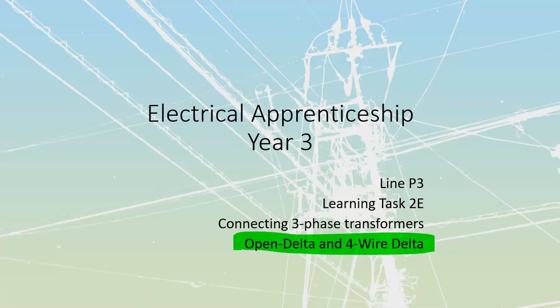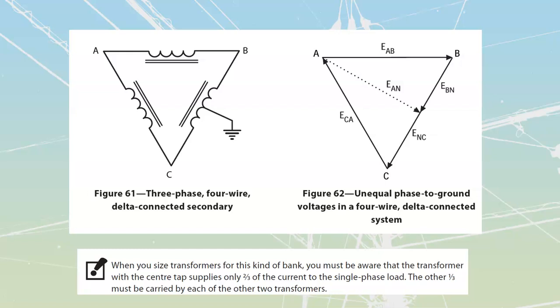What you're able to do is create a special type of system. One of these over here, which is going to be a 4-wire delta system that is fed as a delta system, but it's also going to have one of its transformer windings, this winding right over here, center tapped. And although they're rare, you're usually only going to see these on a 240 volt delta type of system. Because if it's a 240 volt delta system, that would mean that if this one is center tapped, we would be seeing values of 120 volts and 120 volts on either side of that for our single-phase system.